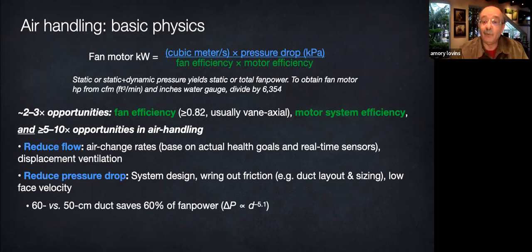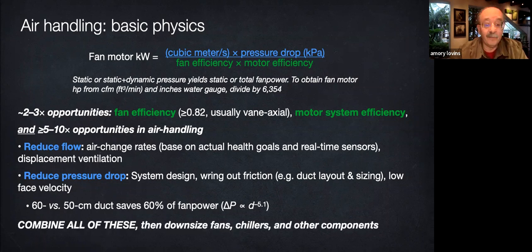Ways to need less airflow include making the building more thermally efficient, or its equipment more efficient, so you needn't deliver as much hot or cold air. Better still, provide comfort radiatively or otherwise without heating or cooling air, since air is a poor heat transfer medium. Eliminate toxic materials from construction and maintenance so the air always stays clean. Enforce non-smoking rules and deliver fresh air in the most effective way. Combine all of these and your air handling equipment will get even smaller and cheaper.